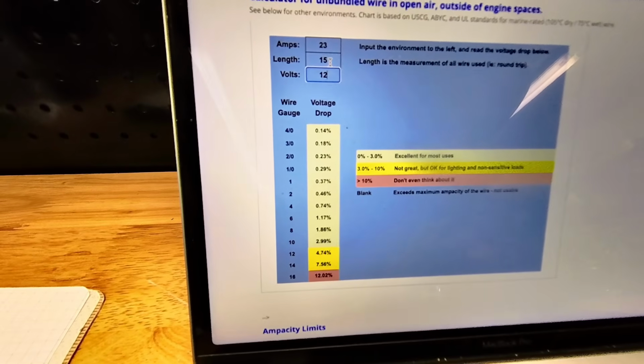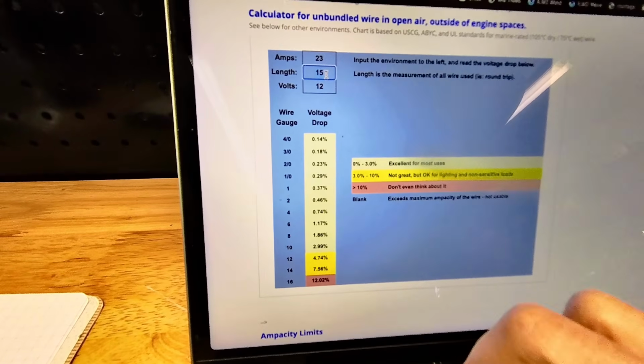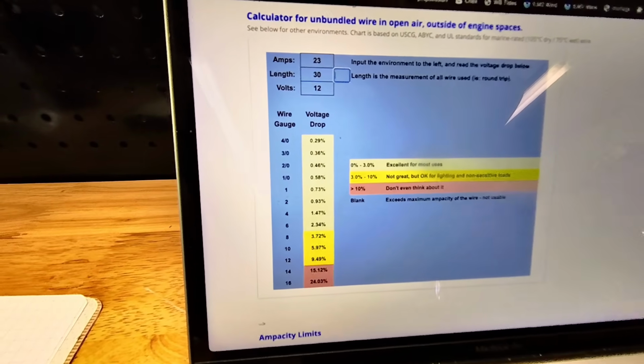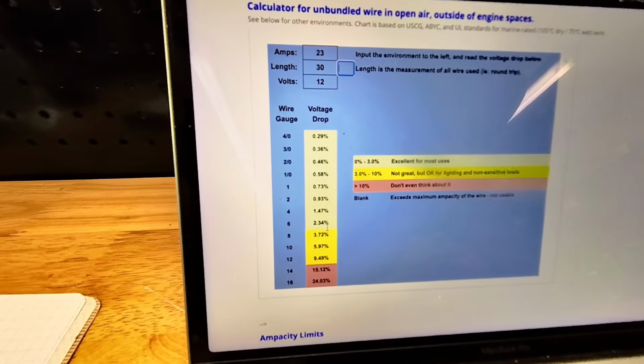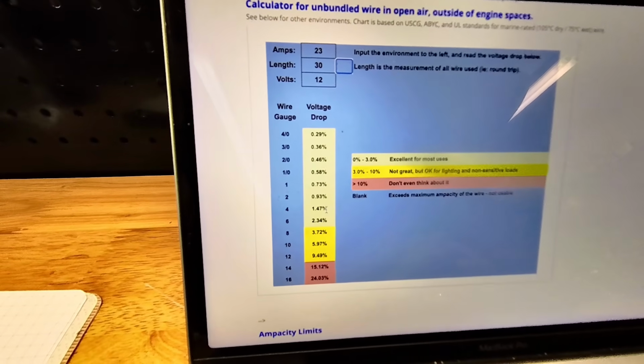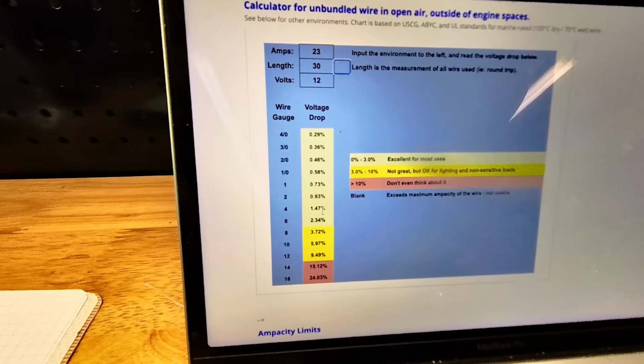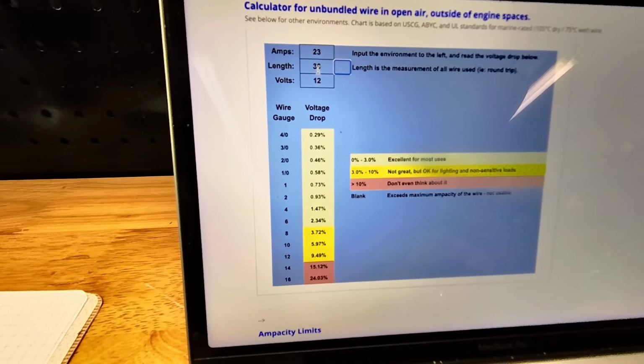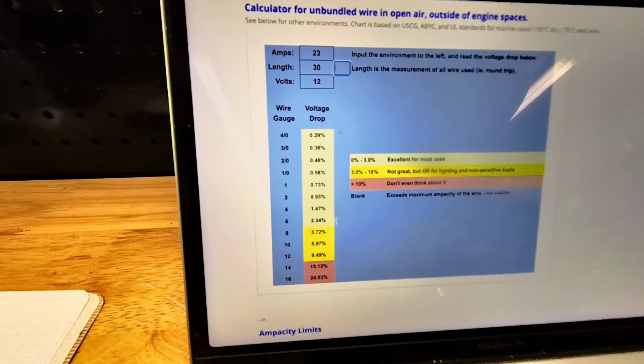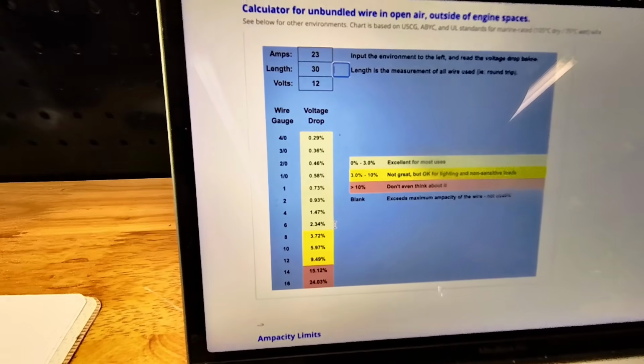Just as a demonstration, if I bump this length up—let's double it to 30 feet—now all of a sudden you see we'd have to get down to a 4 gauge wire for the same level of voltage drop. So it's very important to factor in the length of the cable, because that totally affects the diameter, the size of the cable you'll need.